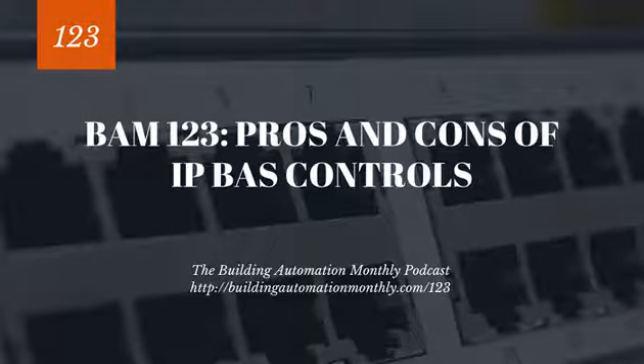With all of that being said, though, this is kind of our first step here, these IP controls. And the primary protocol we're going to be concerned with when we're dealing with IP controls is BACnet IP. Whether you like it or not, whether you're a diehard other protocol fan, BACnet IP has captured the market. I mean, they have dominant market share when it comes to protocols. Now, I'm not saying BACnet IP is the best. That's not my personal stance, but it is the most prolific and the most widespread protocol. Folks are like, hey, what protocol should I use? You don't really have much of a choice outside of BACnet IP. I mean, sure, there are other protocols out there, but they just don't have the line card. They don't have that product depth that BACnet has.